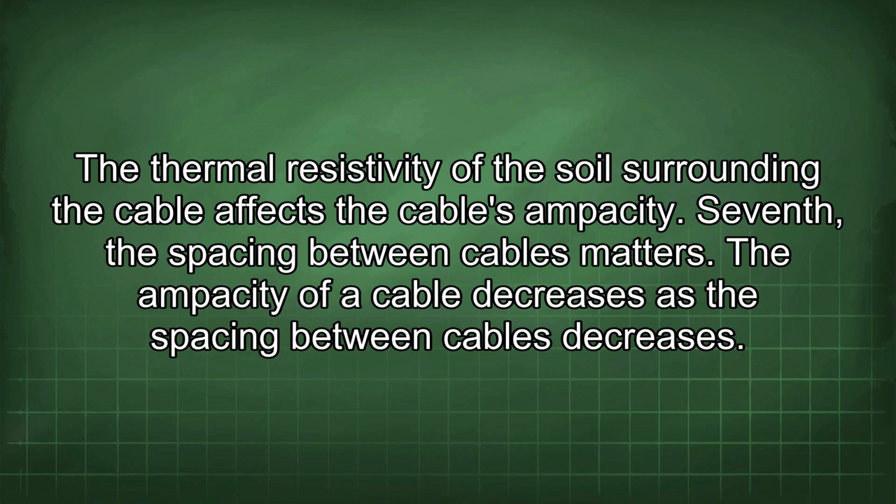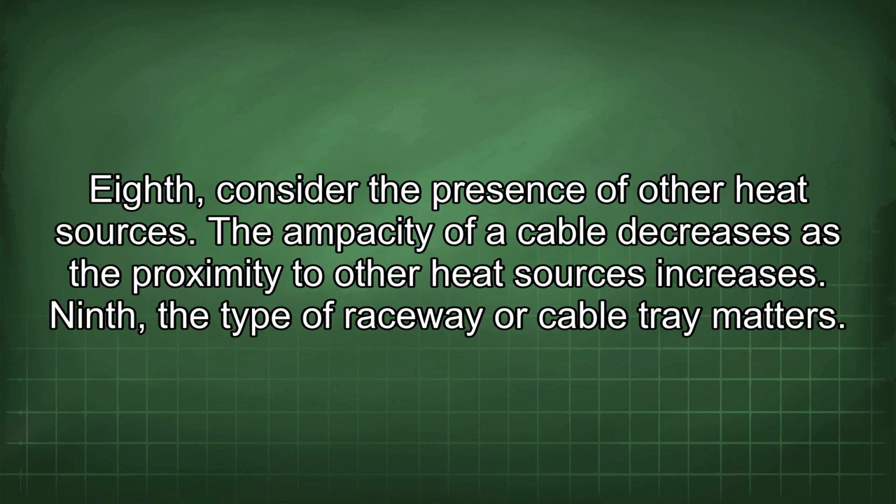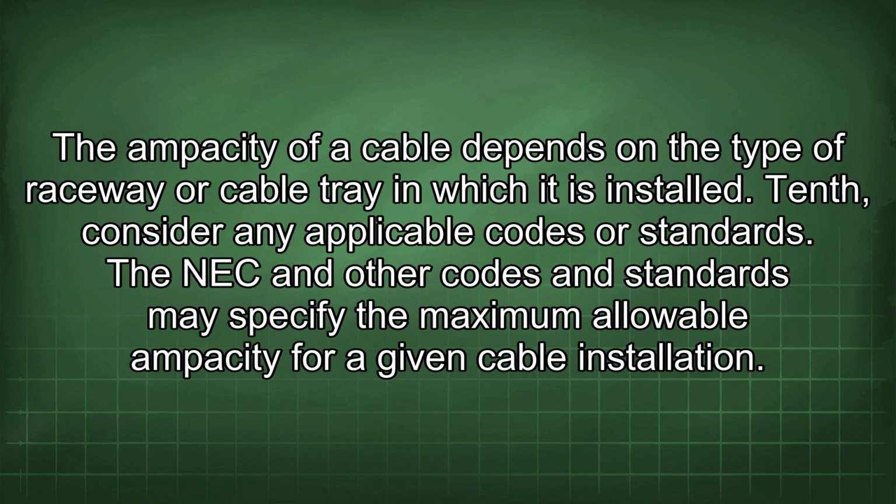Seventh, the spacing between cables matters. The ampacity of a cable decreases as the spacing between cables decreases. Eighth, consider the presence of other heat sources. The ampacity of a cable decreases as the proximity to other heat sources increases. Ninth, the type of raceway or cable tray matters. The ampacity of a cable depends on the type of raceway or cable tray in which it is installed.